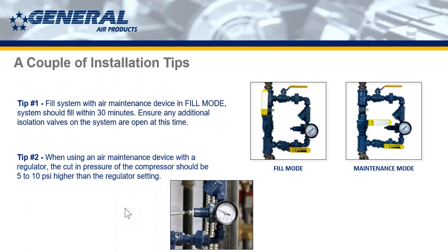There's a big advantage there though from a compressor runtime. If you were to put the regulator, let's say again at 40 PSI, so that you have 40 PSI in your system, and you have a compressor that can go up to 60 PSI, turn it up to 60 PSI, and let the regulator hold that back. And what happens is you have a lot more stored volume of air. So as the system leaks, it weeps into the system, but it doesn't necessarily draw from the reserves, and it doesn't necessarily cause the compressor to run every time that the system needs some more volume.